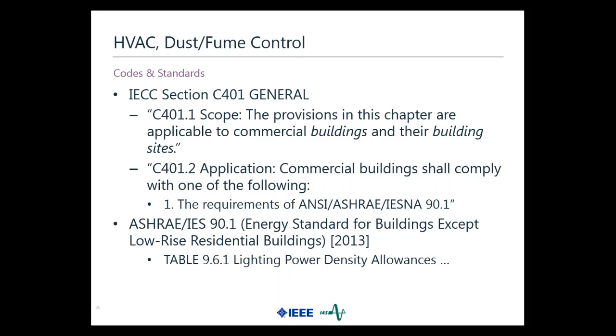Now, one of the things that I get into, particularly when you've got standalone electrical rooms, and we had this on the Houston project that I mentioned, the smoke detectors were interlocked with the HVAC units for that. And that got me to thinking, where do you actually find that requirement? Well, the requirement that I found was NFPA 72, but you'll notice that it doesn't actually tell you you've got to interlock it in this case. It just talks about various types of interconnections.